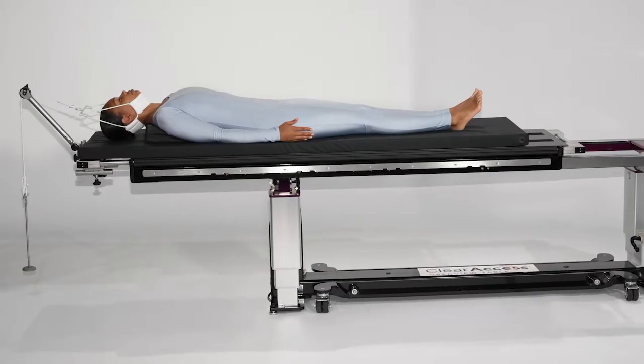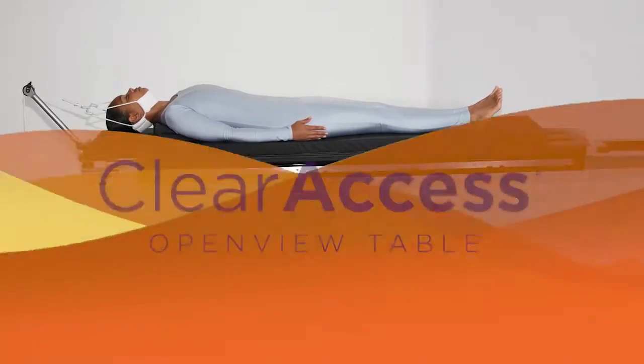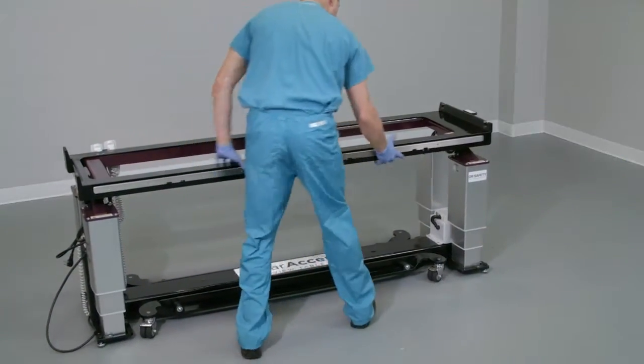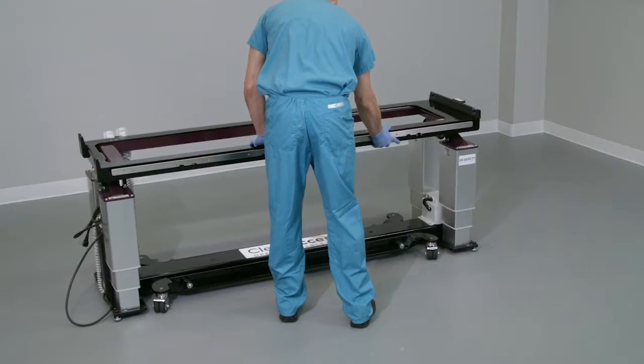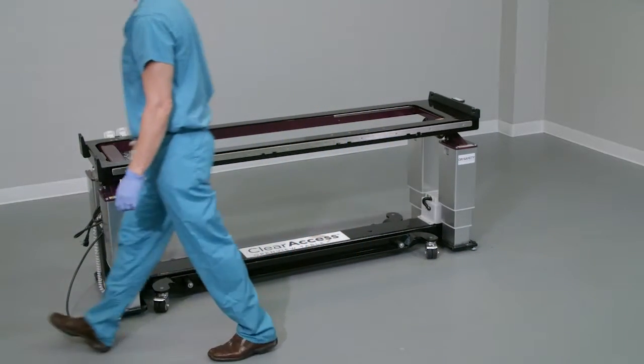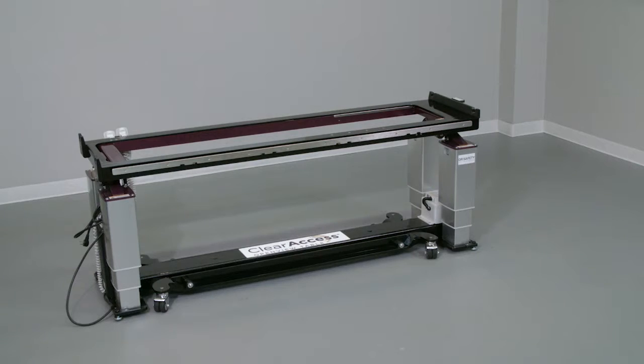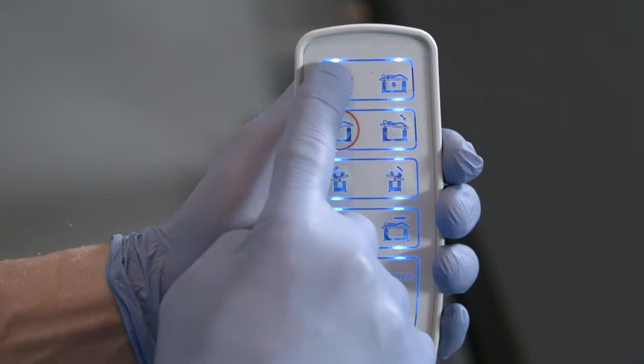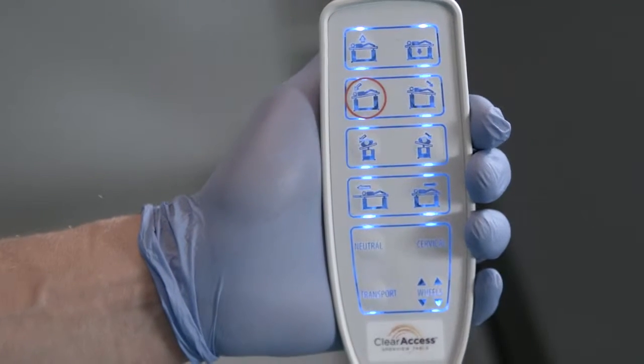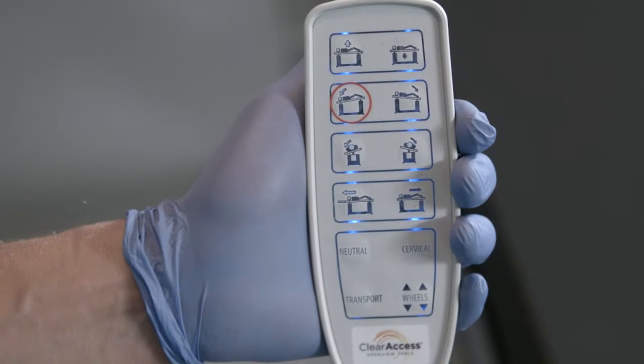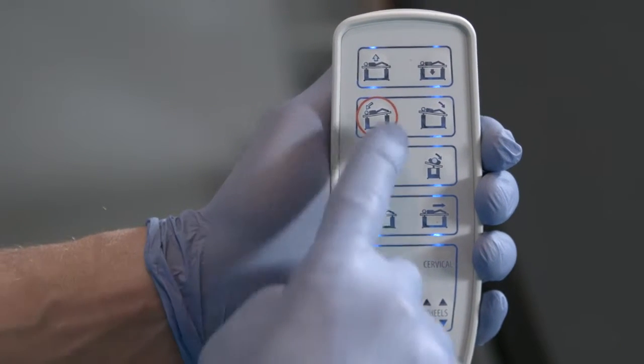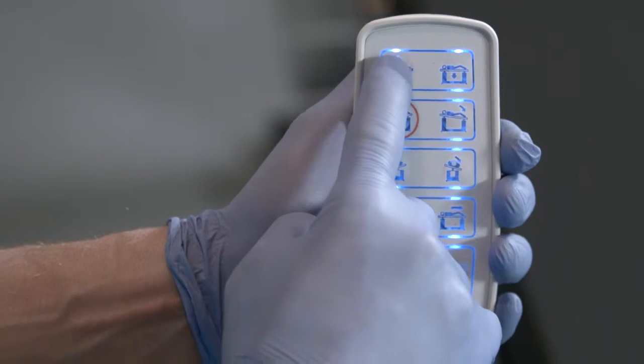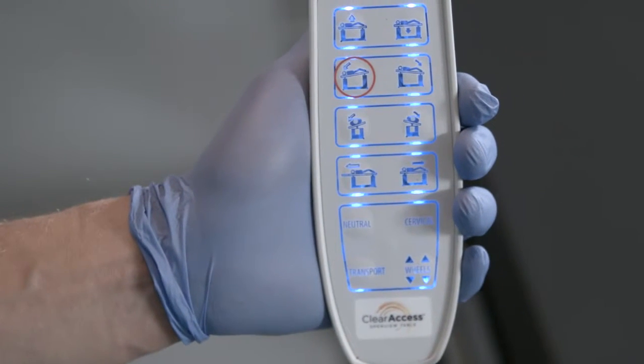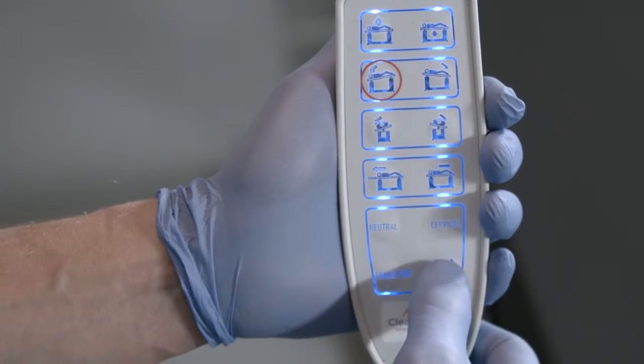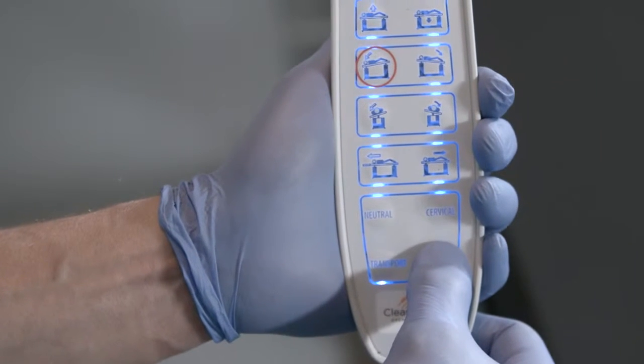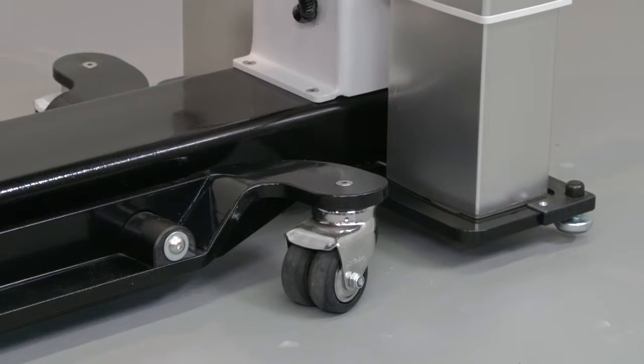disc fusion (ACDF) procedures. Move the Clear Access table to the preferred location in the OR. To lock the table to the floor, press any button on the hand controller to wake it. Both hand controllers will auto-sleep if inactive for 30 seconds. Press any button to reactivate, and then lock the table by pressing the wheels button firmly once and releasing. You'll note an audible beep as the table is lowered to the ground, warning caregivers to keep personnel and equipment clear of the table.